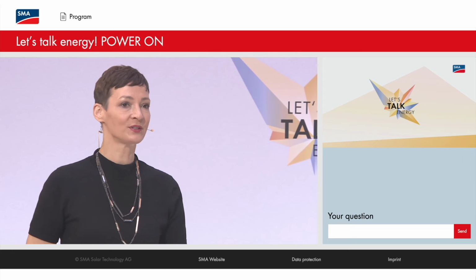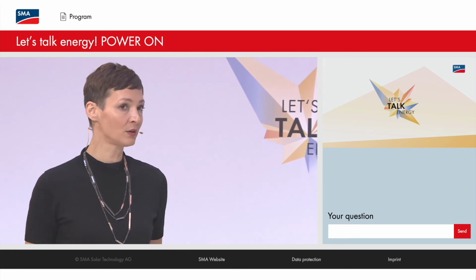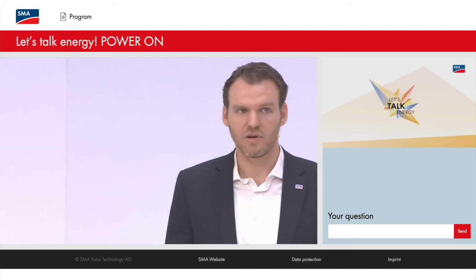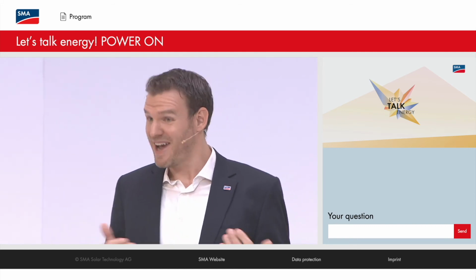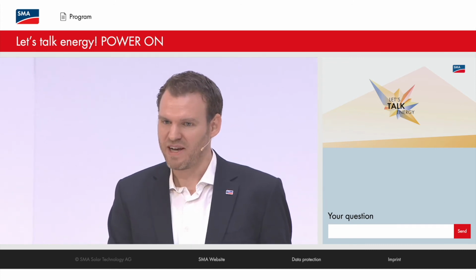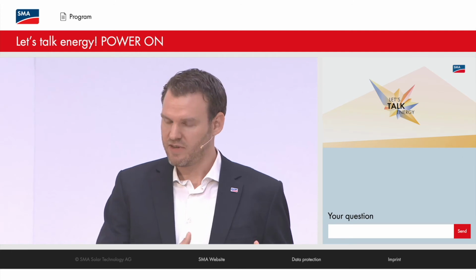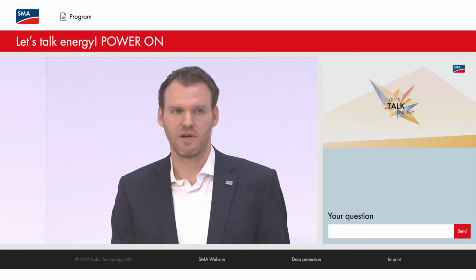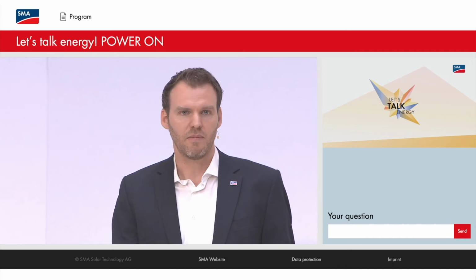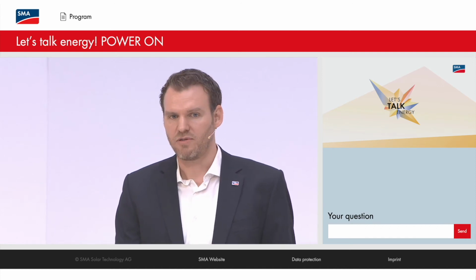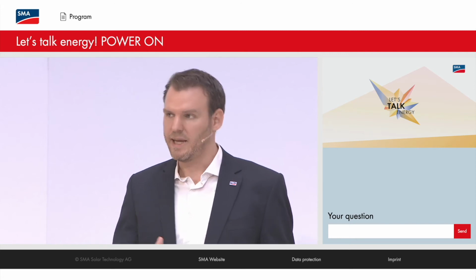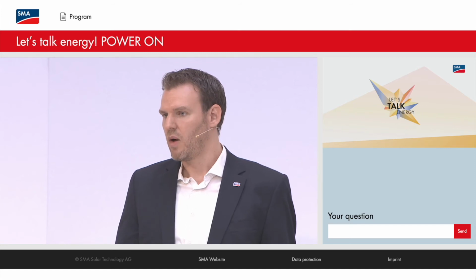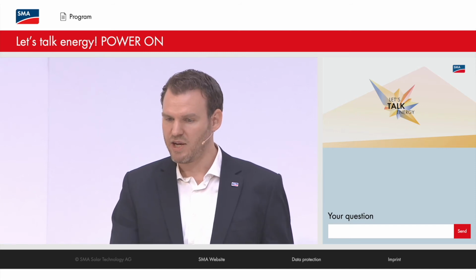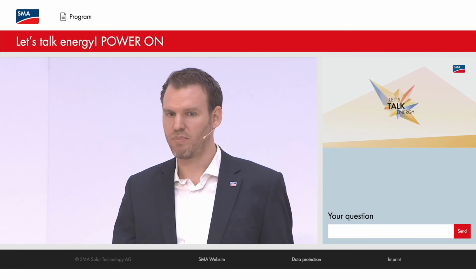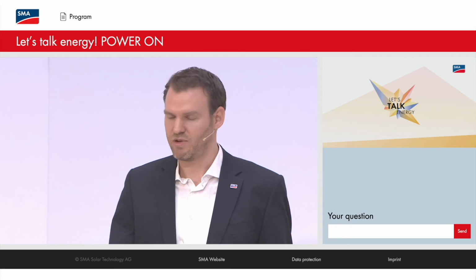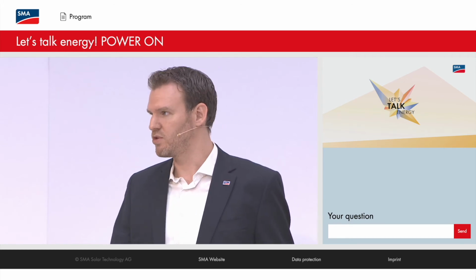So Carsten, first one for you: what's better or more economical for PV and storage? That was kind of the last slide, so again, like a good lawyer would answer, it depends. But if it's really about capex saving and having a very large PV array with maybe a limited grid connection point, then DC coupled has quite some advantages, as I mentioned with the round-trip efficiency. There's also an advantage in some markets with restrictions on nameplate rating of inverters, like in the US, where utilities don't allow a combined nameplate rating larger than the grid connection. DC-coupled helps there because, well, it's a stupid rule, but it helps you actually get grid access.